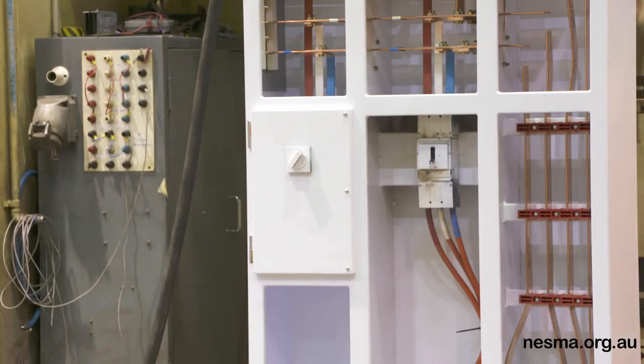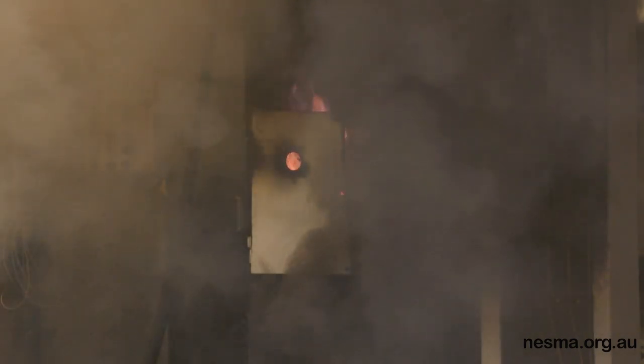And so in that instance, we're looking for an IP2X rating to that unit. The aim is that that's the minimum IPX requirement for an assembly that's in service. So if you're taking the board out and there's no requirement, then the board only needs to meet an IP1X, where a 50mm hole is acceptable. And if you're taking it back into service, then the whole assembly must meet the IP2X requirement. So I think it's fairly graphic.